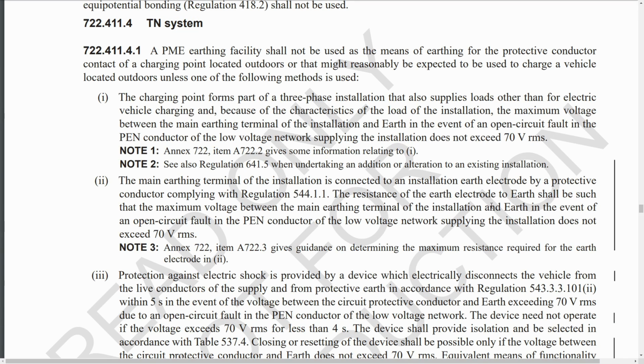This is where you have a 3-phase installation that also supplies loads other than electric vehicle charging, and because of the characteristics of the loads in the installation, the maximum voltage between the earthing terminal of the installation and earth does not exceed 70 volts. So what this means in practice is you've got a 3-phase installation which has balanced loads connected to it 100% of the time. Now this is an incredibly unlikely scenario. It does not apply to domestic installations because virtually no domestic properties have 3-phase supplies, and even the ones that do, it's not going to be a perfectly balanced load all the time.